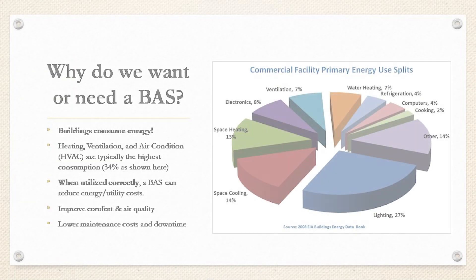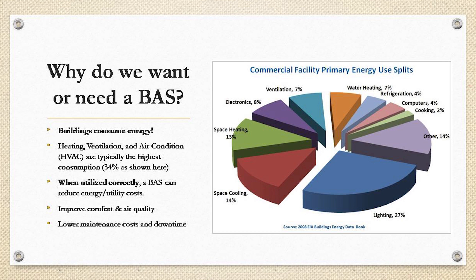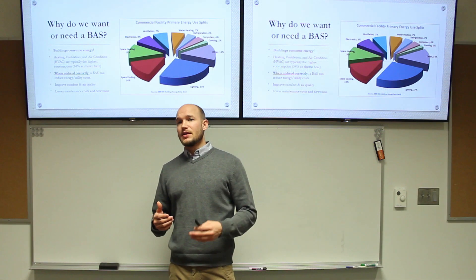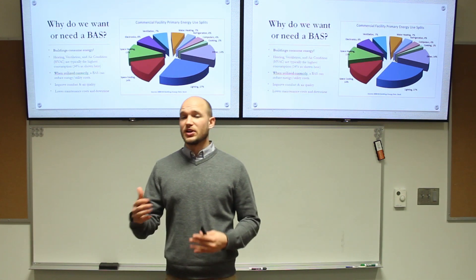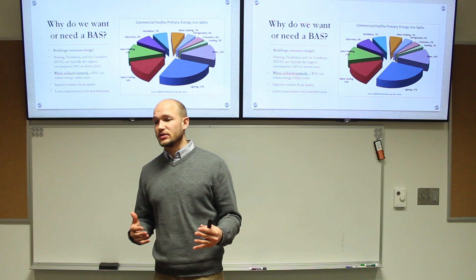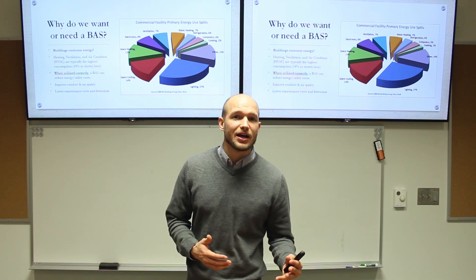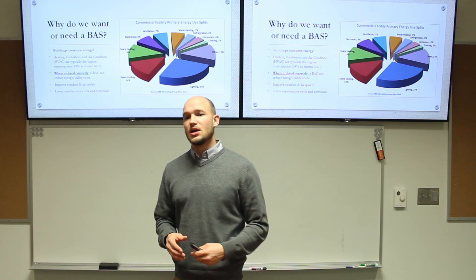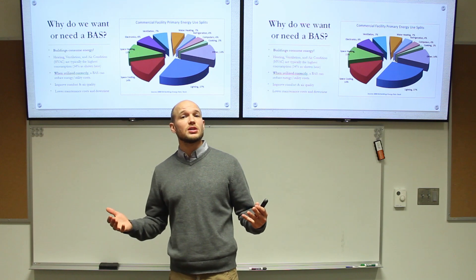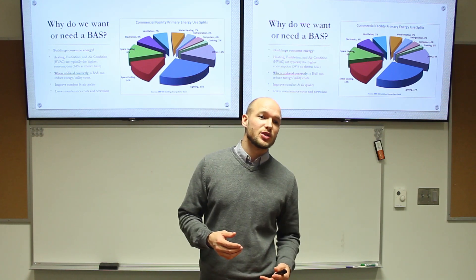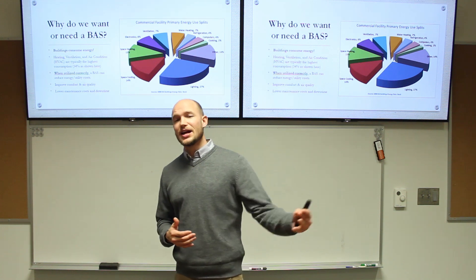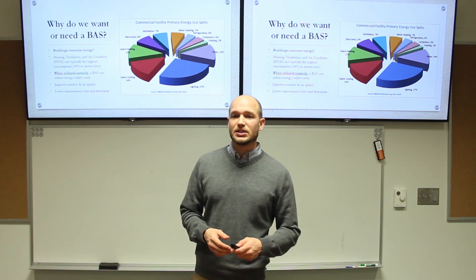Lower maintenance costs and downtime — this is huge. You can set up reports, alarms, notifications, and trends, which can help maintenance control realize when they need to change an air filter, monitor different airflow sensors, compressor run time, and scheduled maintenance times. You can also look at the system remotely to see what the issue is before going on the roof or driving out to a facility, so there are a lot of benefits there.